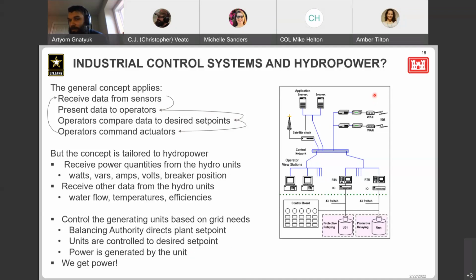This picture is pretty similar to the last one, but tailored more toward hydropower. We've got our generating units down here, some protective relaying that goes up to an RTU cabinet, and IO tied to that RTU cabinet, feeding into a control network where everything's connected. We might get some data from a balancing authority, like how many megawatts they want at this time, how many VARs we need to produce, or how to support the voltage on the switchyard. We also have operator view stations, where the operator sits and views what's happening at the hydro plant.